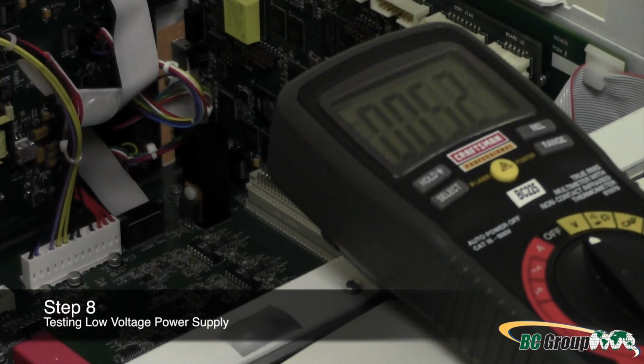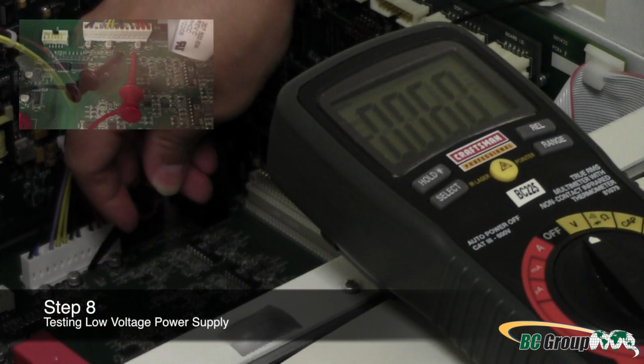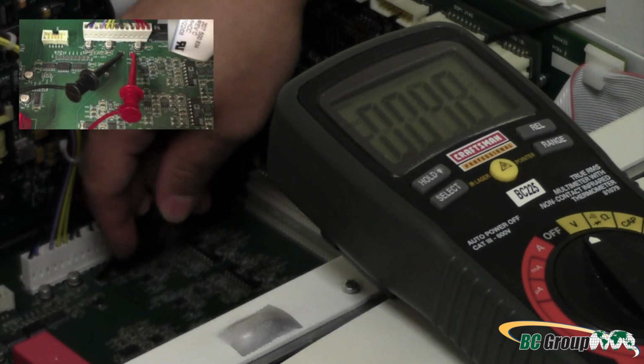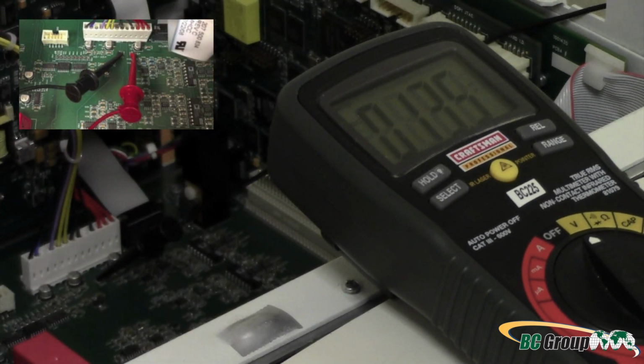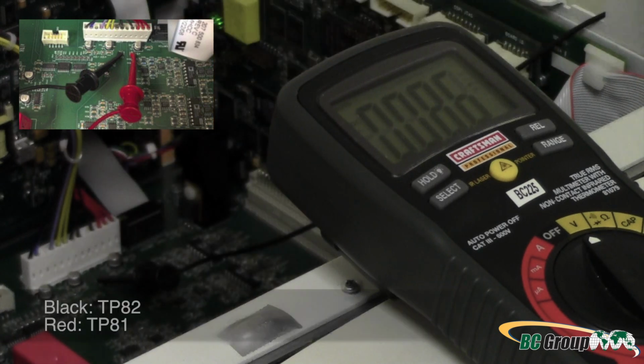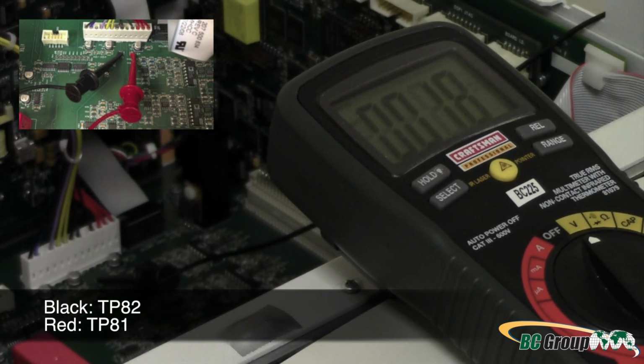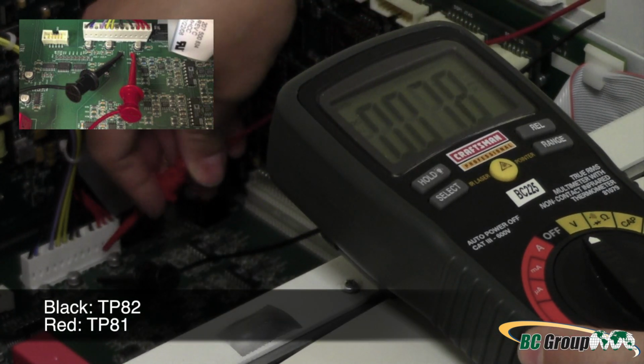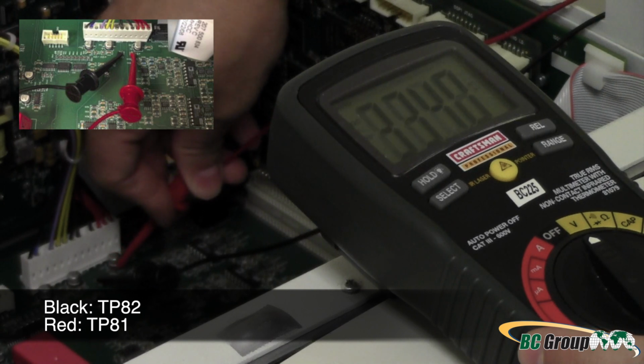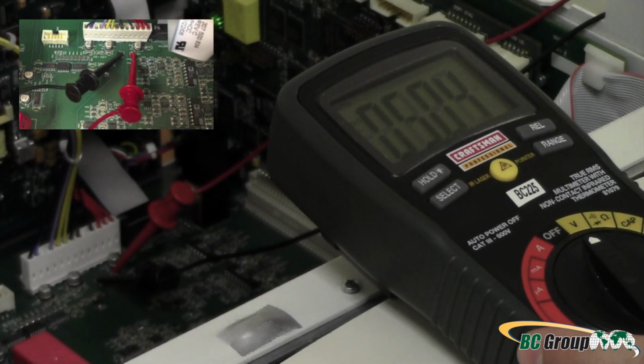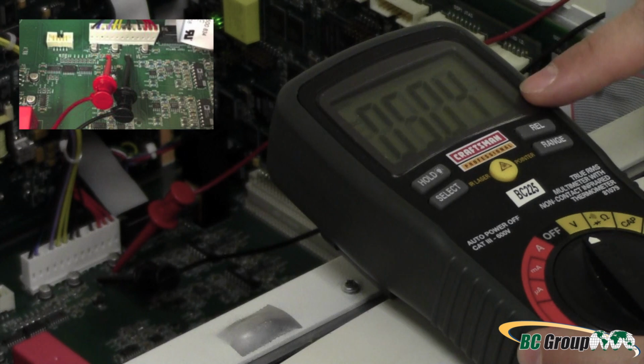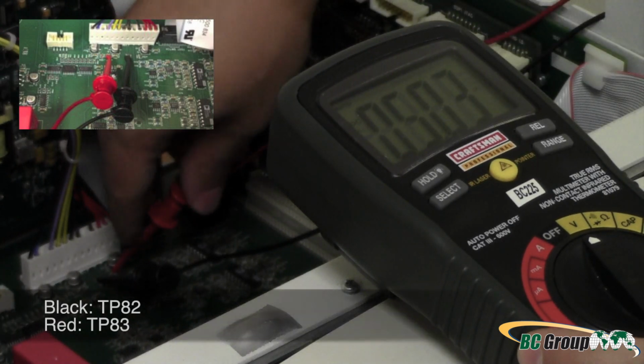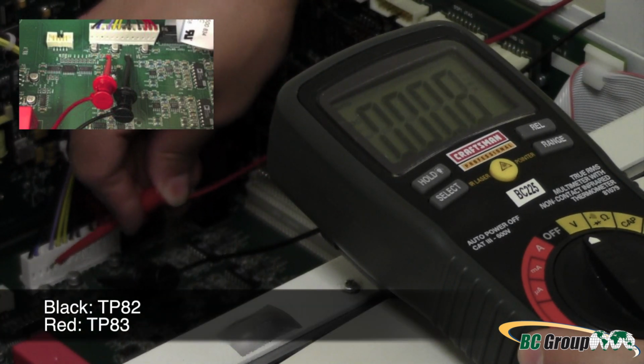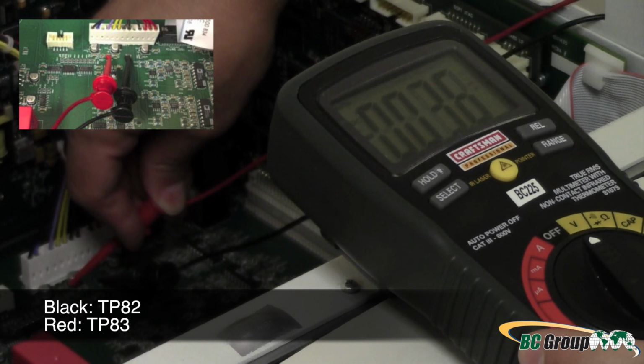Step 8. Testing the low voltage power supply. For this test, you will need a digital multimeter set to DC volts mode. Connect the multimeter's negative test lead to TP82 on the RF board. Connect the multimeter's positive lead to TP81 on the RF board. This should read within 5 to 5.20 volts DC. Connect the positive lead to TP83 on the RF board.